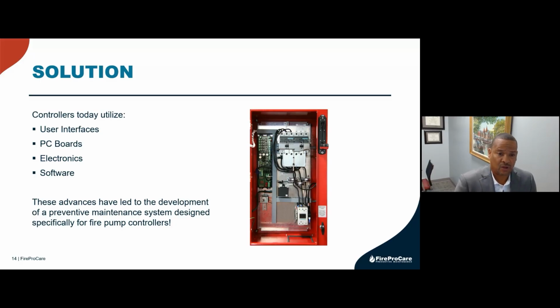I remember back when I was in field service and I would travel around the world, one of the things we used to have to do was take voltage and current measurements while the system was running. Before you had these smart control panels with the interfaces, we literally had to open the door while the pump was running. So there's live voltage and current going through there. Very dangerous situation. We had to stick our hands inside a live panel to take these readings. And that was definitely a safety issue. So the code evolved, and I want to say around 1999 or so, it required controller manufacturers to provide a means to get the voltage and amp readings without opening the doors.